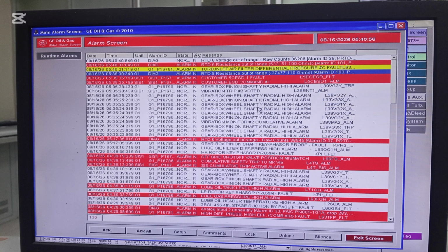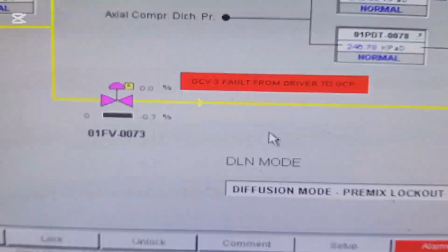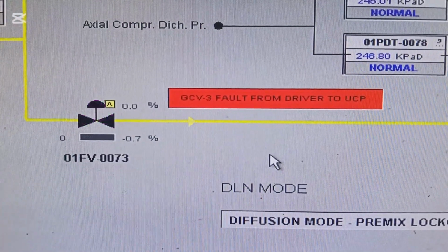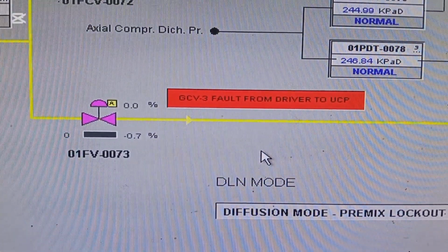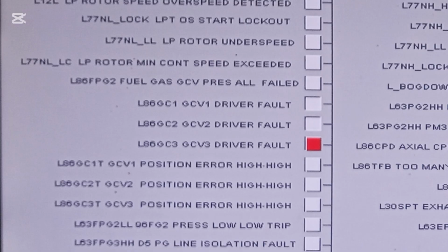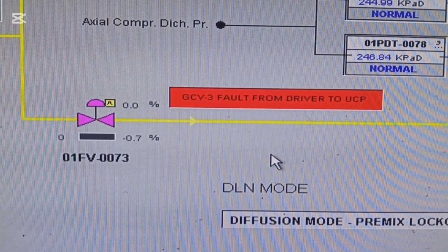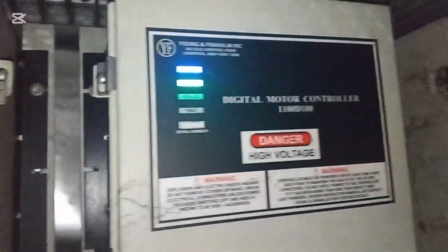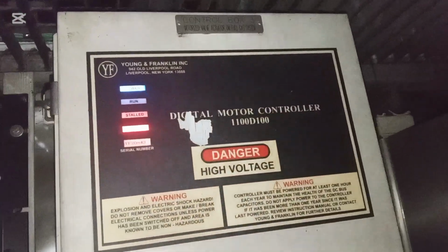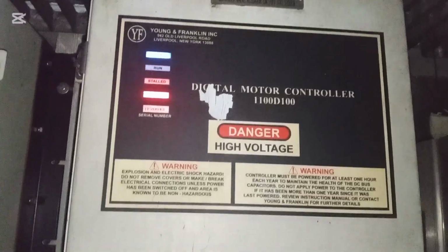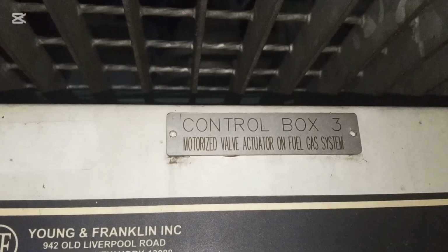Today I will describe and show how we removed the diffusion line valve driver fault of a GE manufactured gas turbine. Suddenly our gas turbine tripped for this alarm, and we first followed all the alarms showing from the DCS panel and then the related controller, that is the driver unit digital motor controller in the field. We followed its alarm and saw that the controller is showing only one signal.